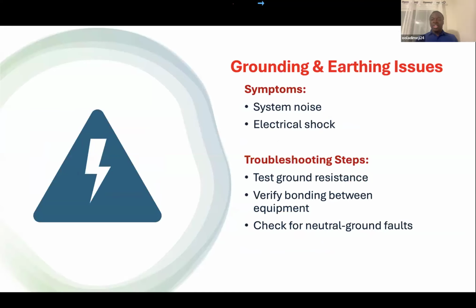Then you have the grounding and earthing issue as well. What your systems will show is system noise. Maybe the inverter system is humming, or when you touch the system, you get an electric shock, or perhaps when you touch any electrical device in the house, like the refrigerator or the cooker, you get an electric shock. And how do you troubleshoot that? You test ground resistance, you verify the bond between equipment, and ensure a good sync between your inverter systems and your equipment.